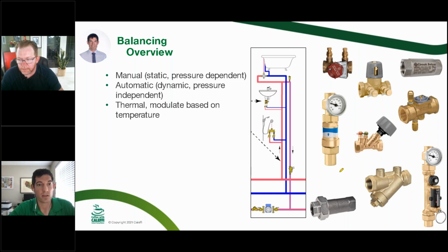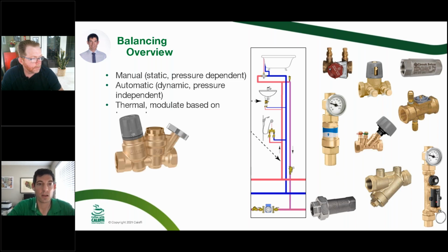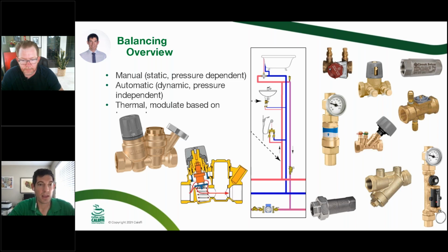So I think the next click in this application for thermal disinfection is this thermal balancing valve, the thermosetter. What this does is you have a temperature solution to a temperature problem. So if you say, in normal operation in this riser, I want to have 120 degrees all the way on the return, you set the knob on the top for that temperature, and it will modulate up and down to allow that temperature to come up and down, not to exceed the temperature that you set there. It doesn't ever close 100%, so you don't deadhead your pumps, but you are automatically keeping up with the demand of the building too.